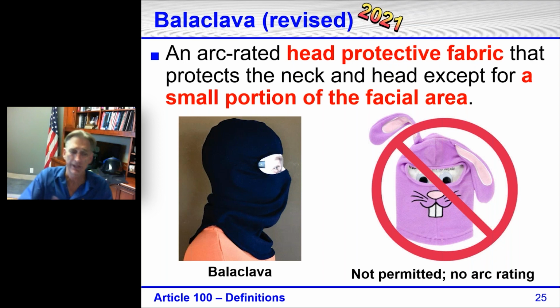All right, so here's the thing. We're getting into a season that's getting cold. If you're out there working and it's cold and you feel like you need to wear a balaclava, until you put your electrical equipment into an electrically safe work condition, you have to wear an arc-rated balaclava. Now, once you've gone through all the steps to put it into an electrically safe work condition and verify that it's there, then you can take off your arc-rated balaclava and put on your bunny balaclava to work outside in the cold, but not until you put the equipment into an electrically safe work condition.